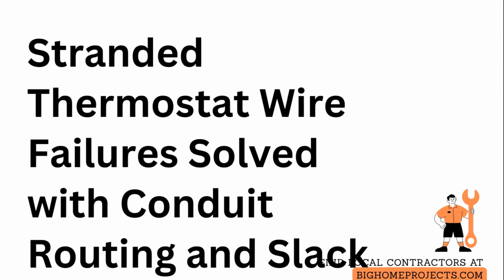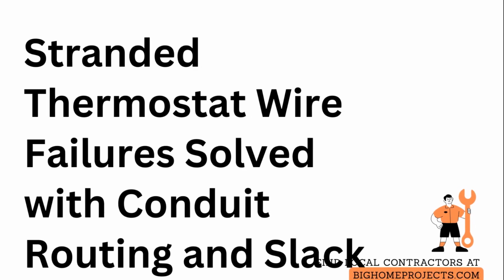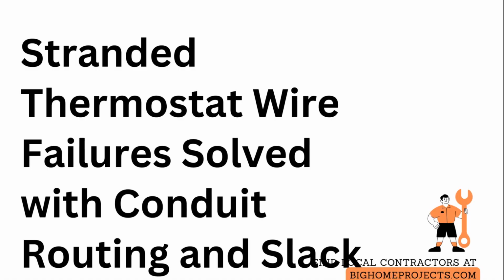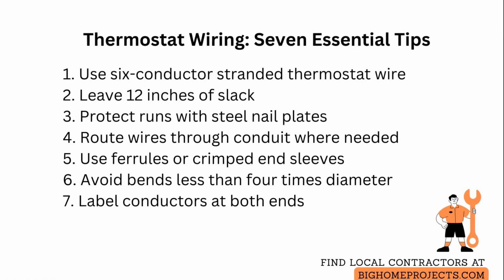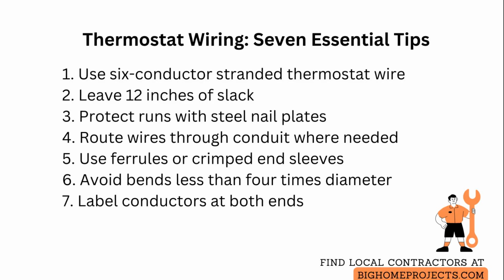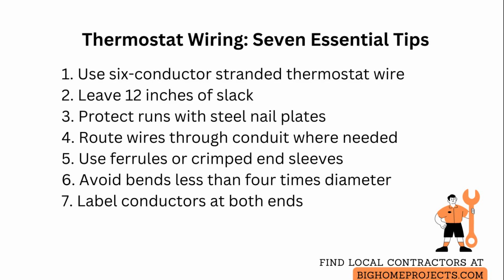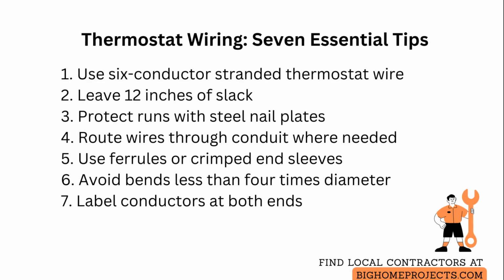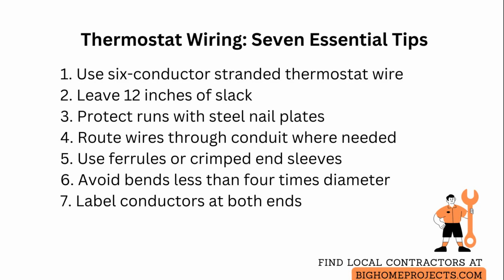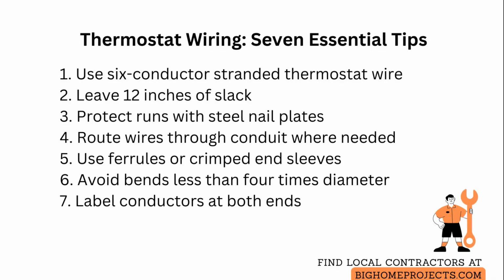Use high-quality multi-strand thermostat wire and proper routing now to avoid repeated failures later. Choose 6 conductor, 24 gauge, stranded copper thermostat wire rated for low voltage HVAC control and run it separately from high voltage cables to reduce induced noise. When pulling wire through walls or crawl spaces, leave a minimum of 12 inches of extra slack at each end to allow for future thermostat moves or terminal reterminations without stressing the conductors.